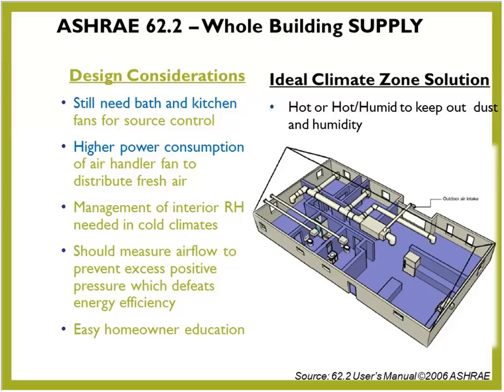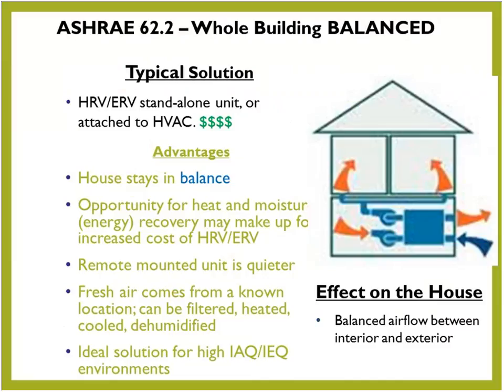In the south with positive pressure, we'd be most of the time pushing air-conditioned air out during the summertime through the building shell. And during the wintertime, there's not as big a delta T. You're not going to get that minus 10 degrees in Florida where you've got those cold surfaces that moist air can be pushed out through. And oftentimes the air-conditioned air inside the building is drier than the outdoor air anyway. So this is probably a better approach for warmer climates than cold climates. Mike, would you agree? Yes, I would agree. Yep.